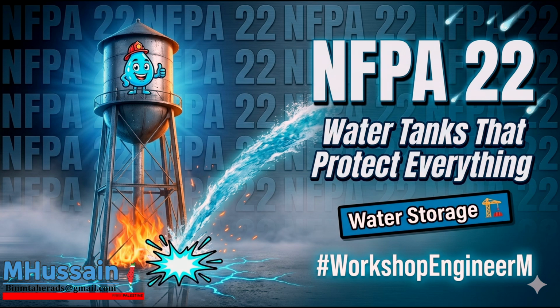The standard is also uncompromising regarding what materials you can use for support. It explicitly forbids the use of interior timber to support or brace these tank structures. You cannot have hidden combustible framing inside the structural envelope. And if an engineer plans to mount a gravity tank on the roof of a building, which is the standard approach in dense urban environments like Manhattan, the building's structural frame must be specifically engineered to carry those maximum loads, and roof mounting introduces severe dynamic engineering challenges, because it's not just static weight anymore.